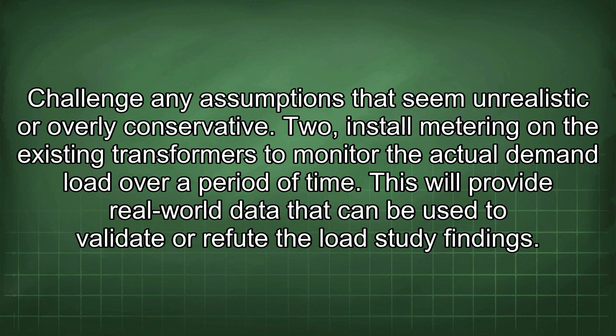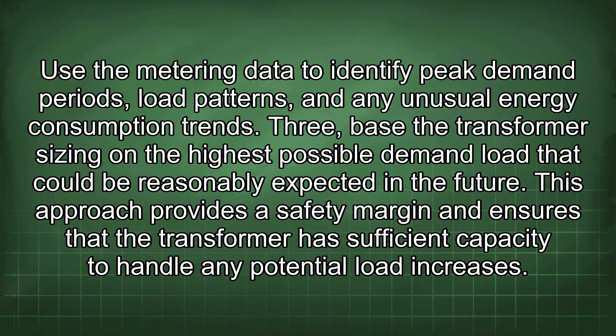3. Base the transformer sizing on the highest possible demand load that could be reasonably expected in the future. This approach provides a safety margin and ensures that the transformer has sufficient capacity to handle any potential load increases. Consider the impact of new equipment, expanded operations, and changes in building occupancy.